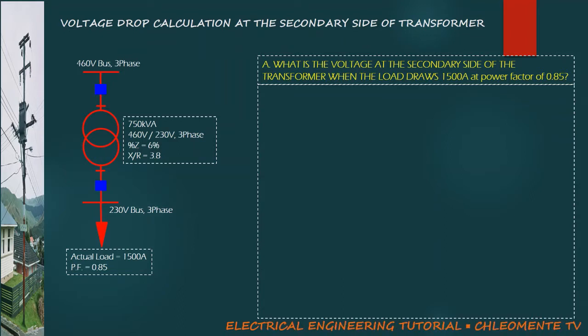In this example, we have a load of 1500 amperes with a power factor of 85%. It is connected with a transformer having 750 kVA rating, 460 to 230 volts, 3 phase. The given transformer impedance voltage is 6% with X over R ratio of 3.8.